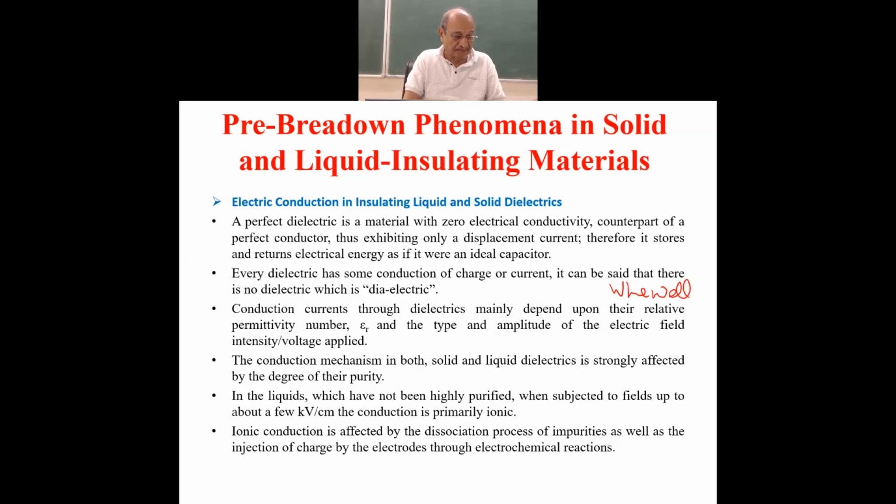Then we've already seen the moisture ingress. Moisture ingress does not only affect the liquid dielectrics, it affects the solid dielectrics also tremendously. Then there may be air pockets or void formation. That could be because of bad quality, bad finish of the dielectric, and these gaseous inclusions.